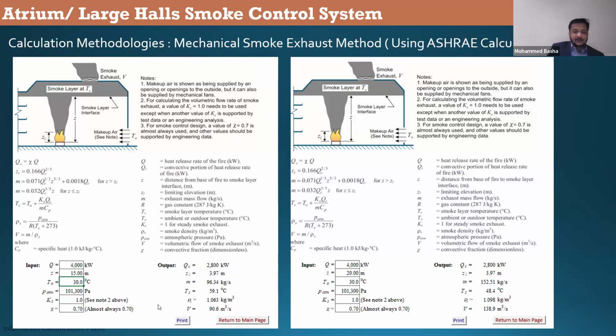So when you use this value, you can see the convective heat quotient is 2800 kilowatt. I told you it is 70% of the Q, so when you multiply by this 70%, you will get this value. Z1, leave it, which is called the limiting elevation, the minimum smoke layer height. TS is the smoke layer temperature, which will be 60 degrees Celsius here.